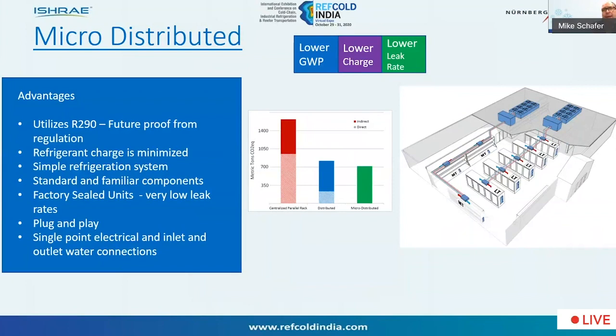The other advantage too is that these types of systems can be made in a factory setting, in the manufacturing process, so that the seal integrity is very good. Very low leak rates. The systems are typically single point electric with just one inlet and outlet water connection. So these are very plug and play, very quick to install. So obviously the advantage, of course, looking at the TEWI calculation, is very evident.